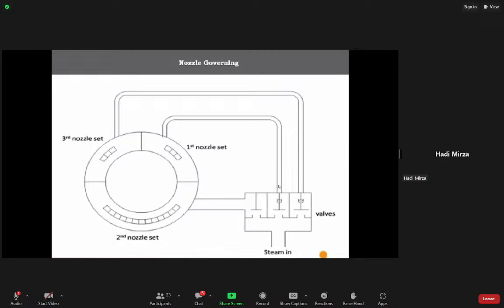Steam inlet is here. At the initial stage, this nozzle will be in operation in partial load. First, this valve will be opened fully, and then the second valve will get operated, and then the third valve will be operated. By this, there will be a play in these valves. The first valve will be opened fully, and then only the second. This is called the lift of the valves. Lift will be designed in such a way that first this valve will be opened, and then only the second valve will start opening.